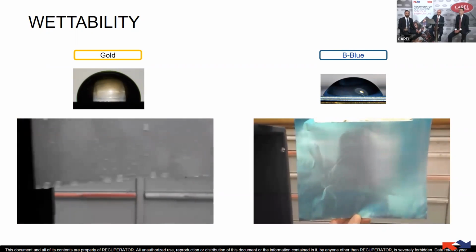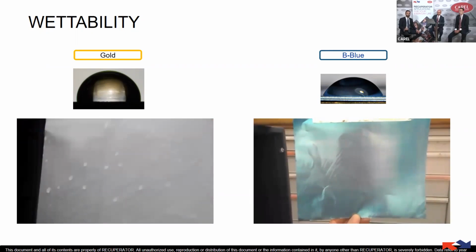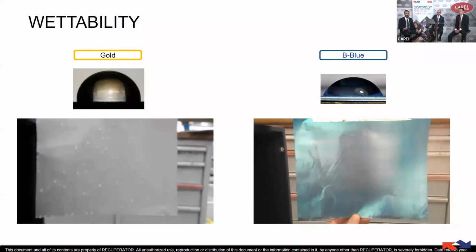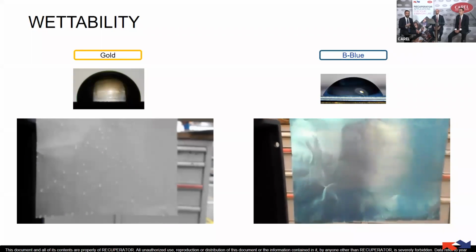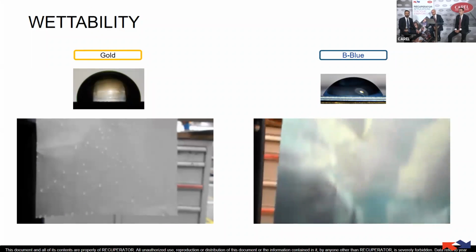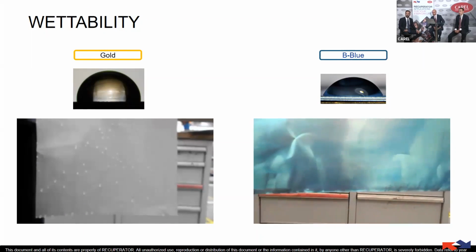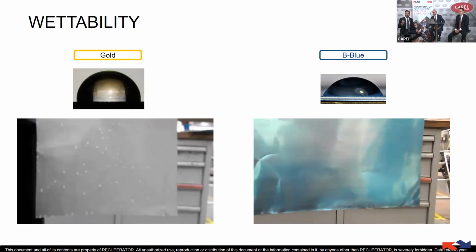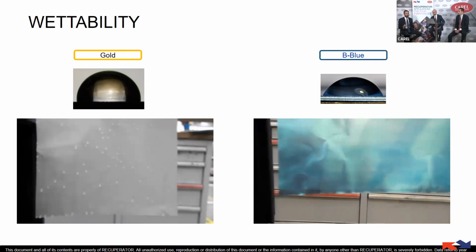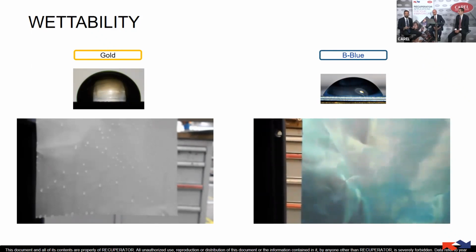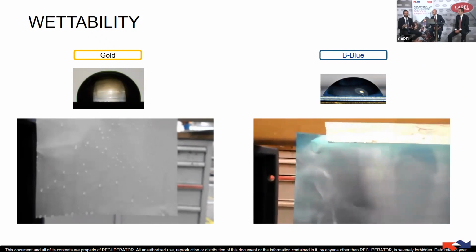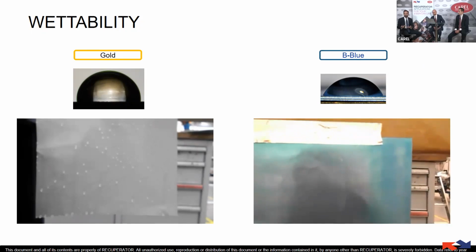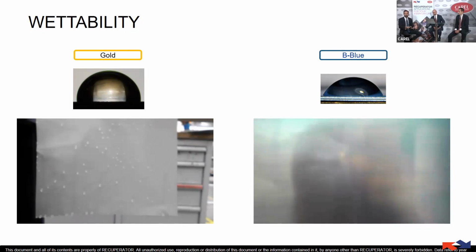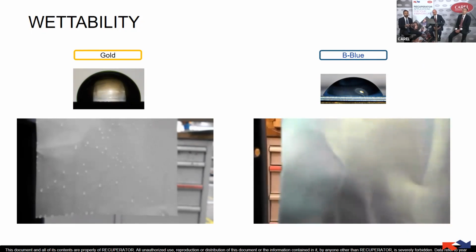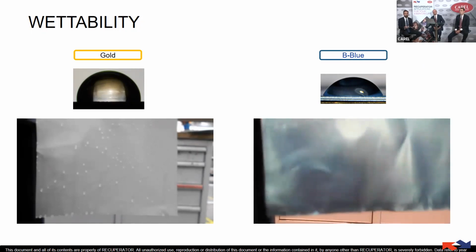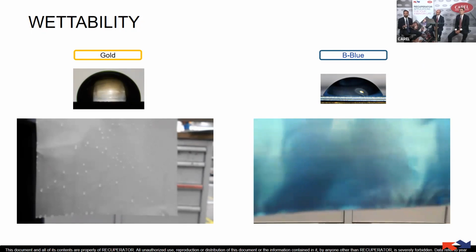Thanks to this film of water, we can have an increase of cooling capacity that we have seen before with the example, that is 10%, 15% more than the standard gold protection. This is really important because we can increase the cooling capacity without increasing the pressure drop, just by using a type of coating. With the pressurized system, we have replaced the wet pad that always has a pressure drop. Then we have a really efficient way.